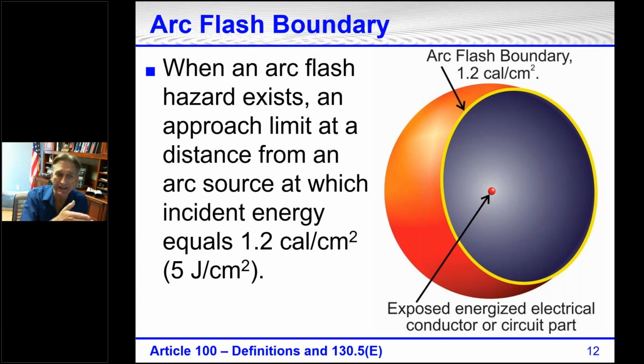And then when that incident energy drops to a level of 1.2 calories per square centimeter, that is the arc flash boundary. Dr. Stoll did the research and calculations on this, and 1.2 calories is the amount of heat on skin that will give a first-degree burn. Sometimes it's called the onset of a second-degree burn. It's not a second-degree burn yet, but it's as close as you can get. Going over 1.2 calories per square centimeter becomes a second-degree burn. That's why the arc flash boundary is based on getting a first-degree burn if you're standing right on the boundary.